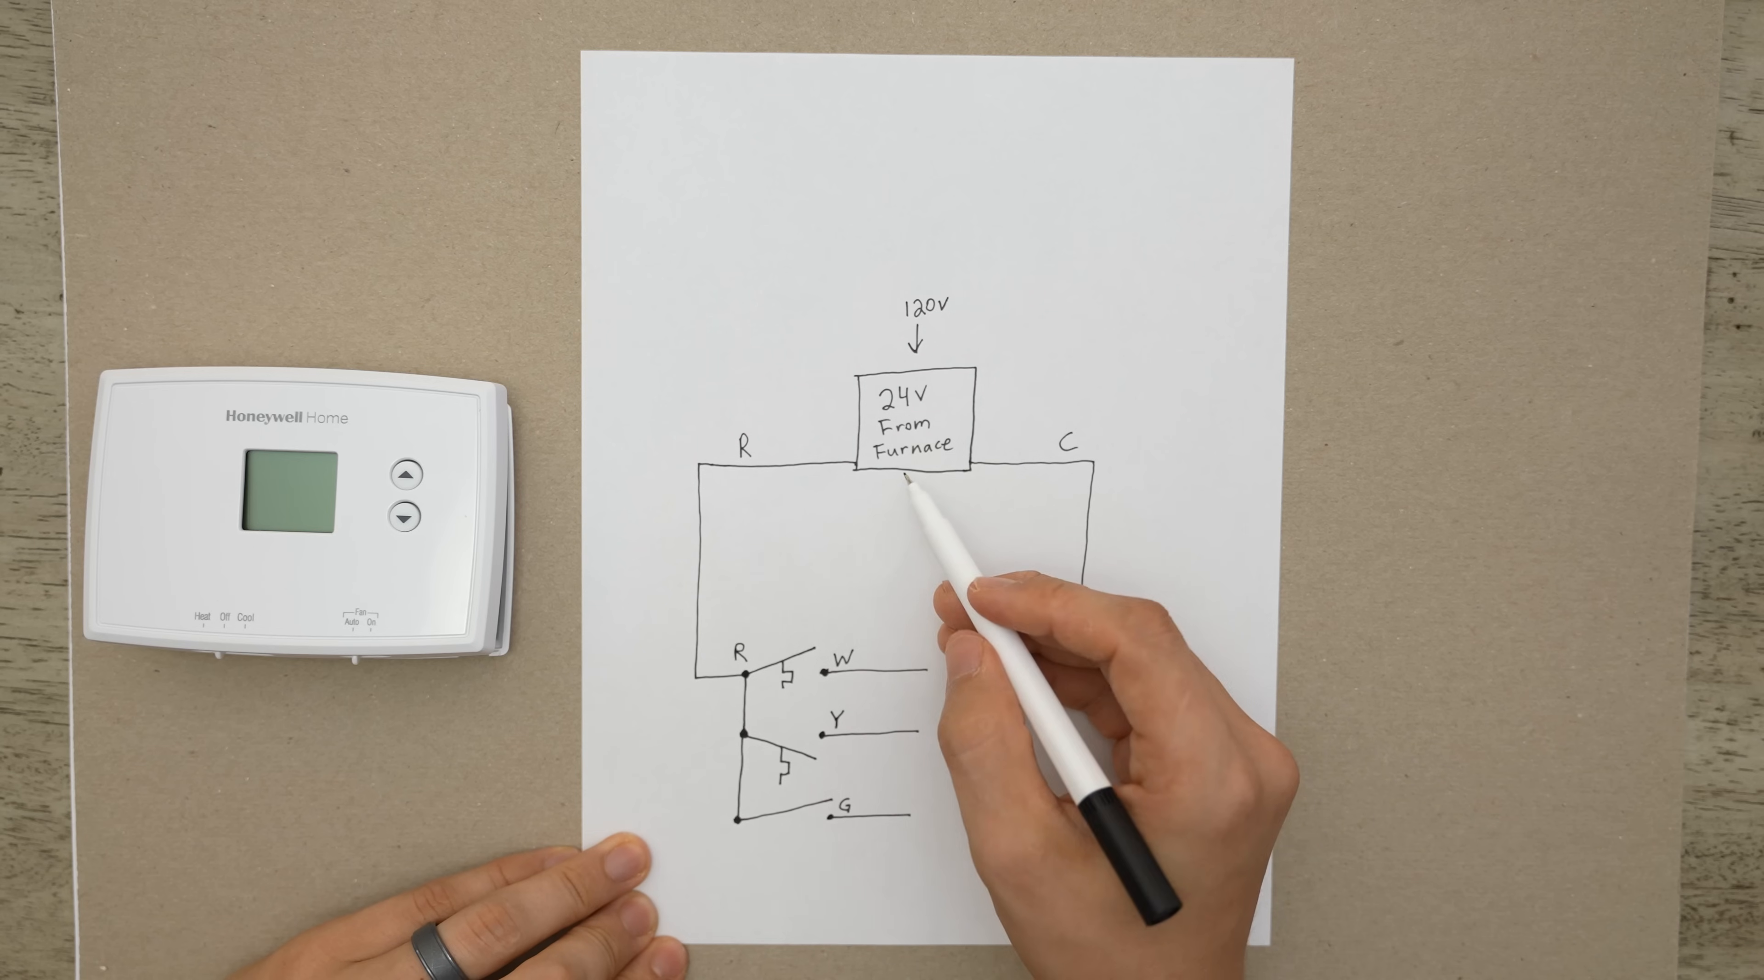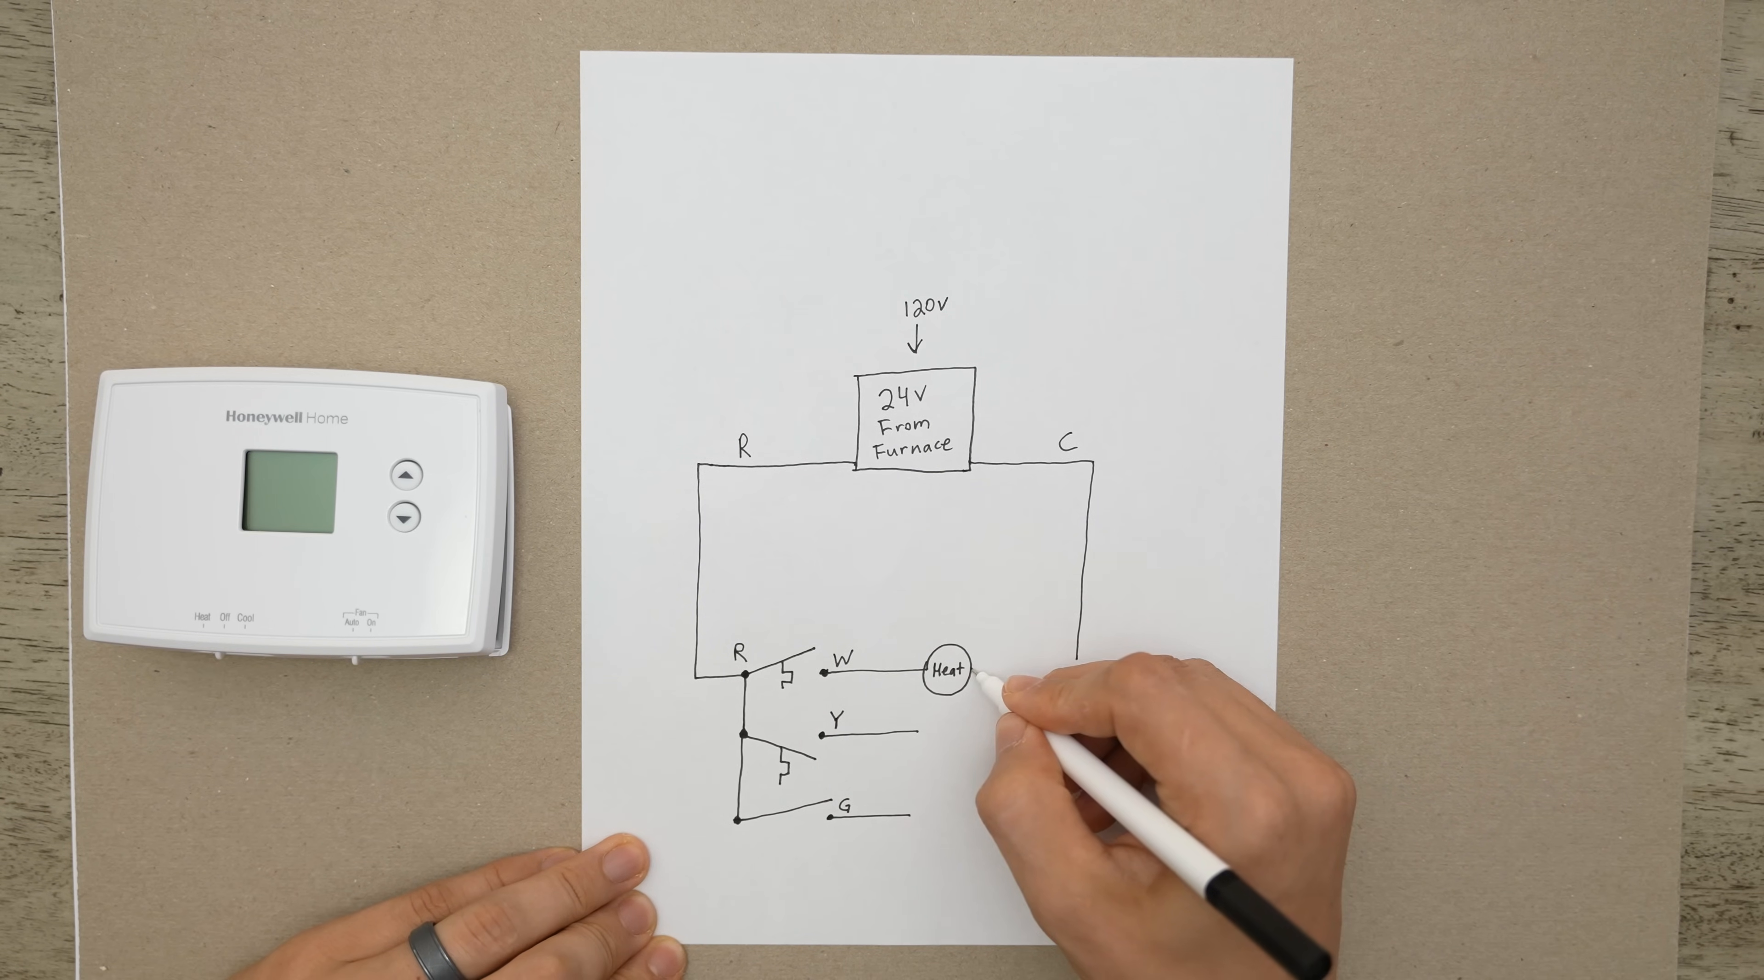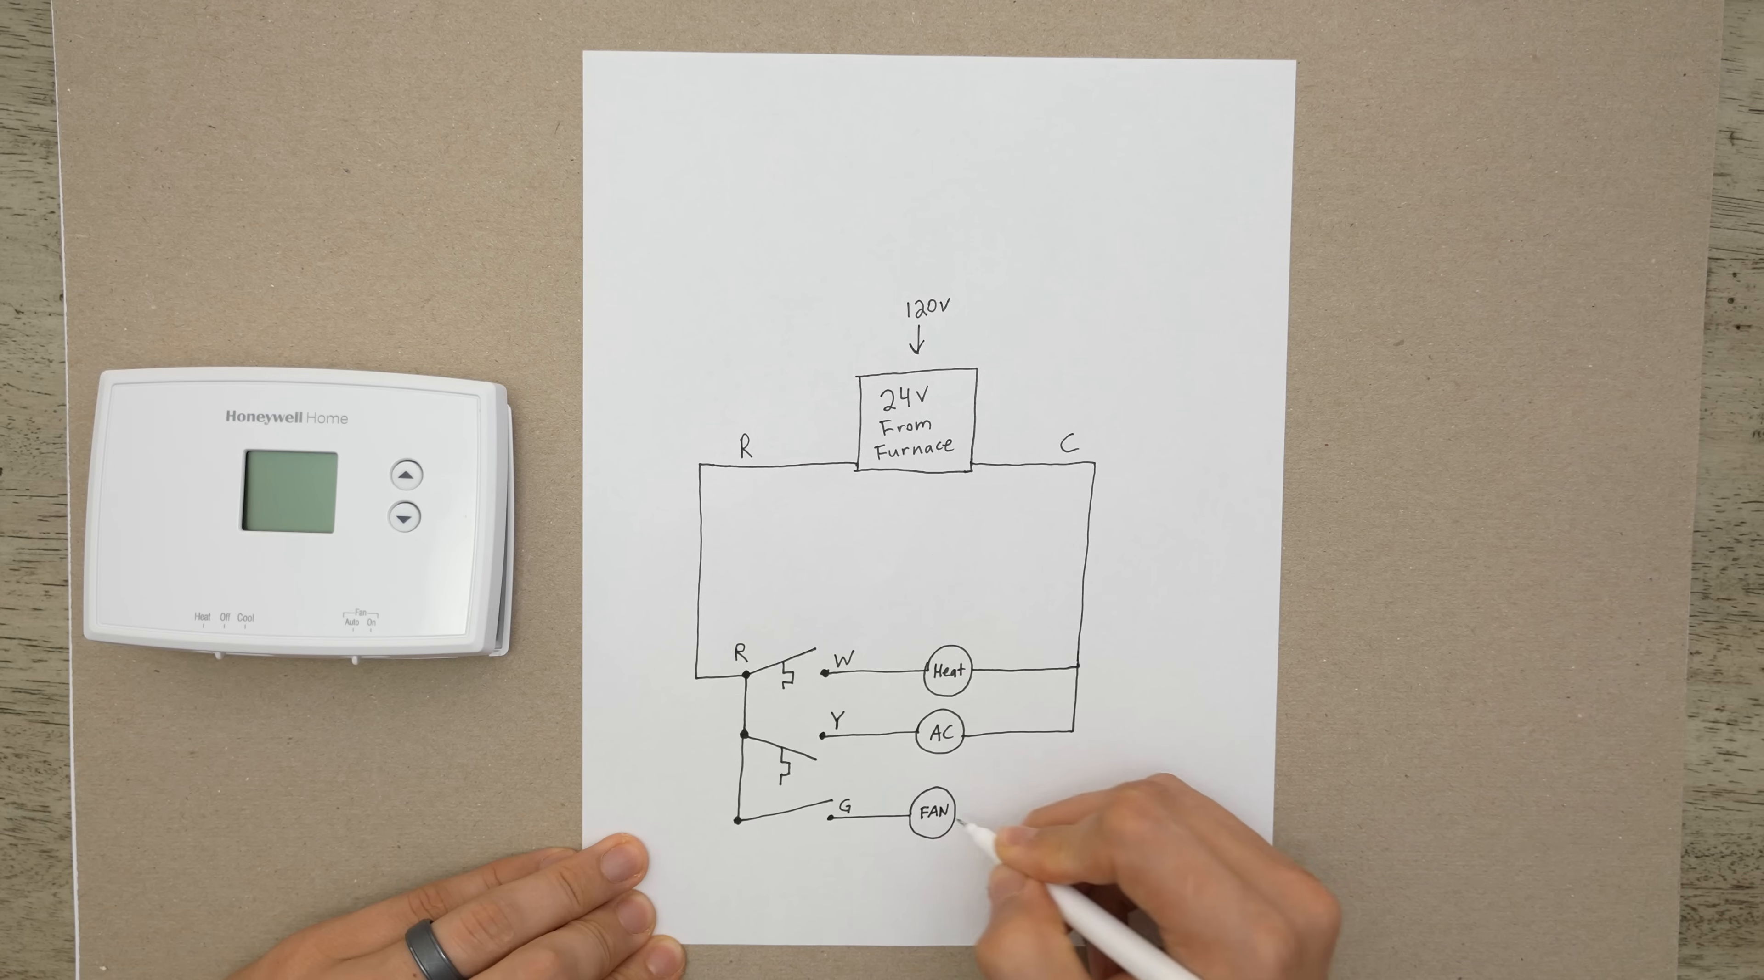So our furnace is sending power to our R terminal and whenever any of these switches close it sends power down that line. So W is going to be our heat source. So let's just put a big circle here and name it heat. So when this switch closes our furnace turns on. When Y closes, when this line over here closes, then our AC comes on.